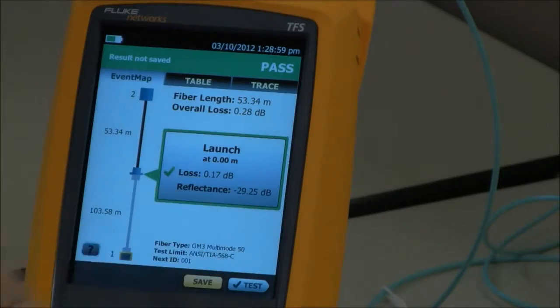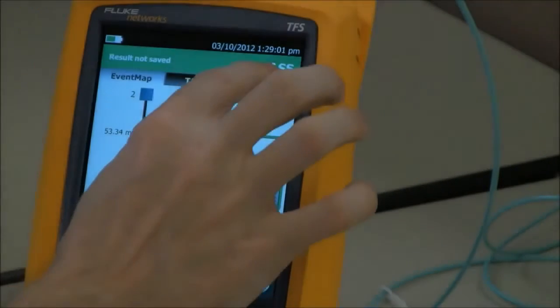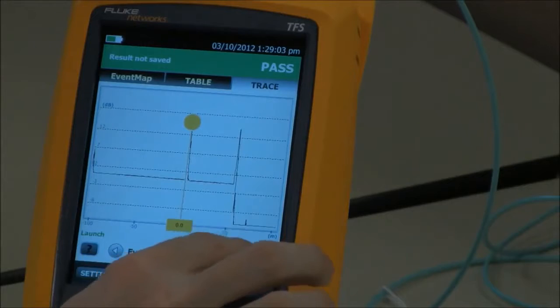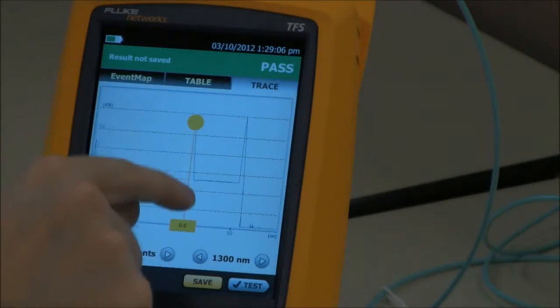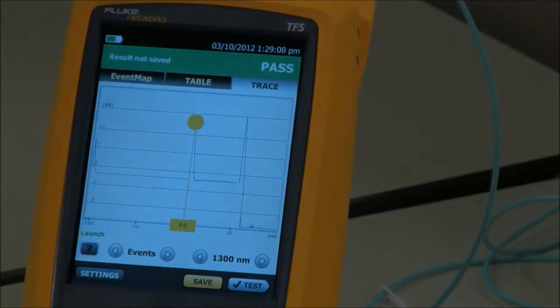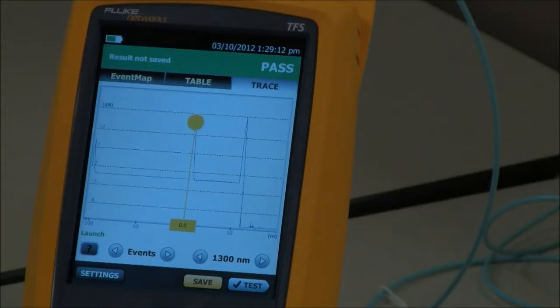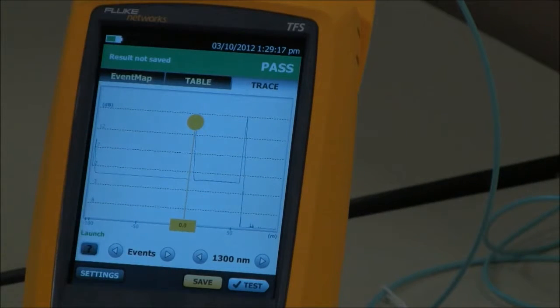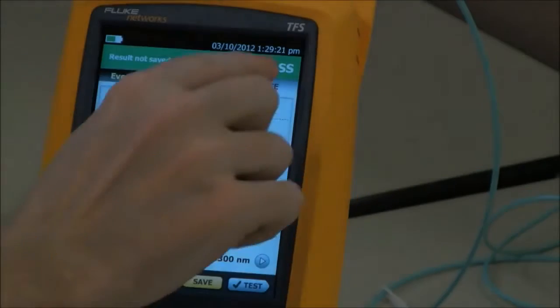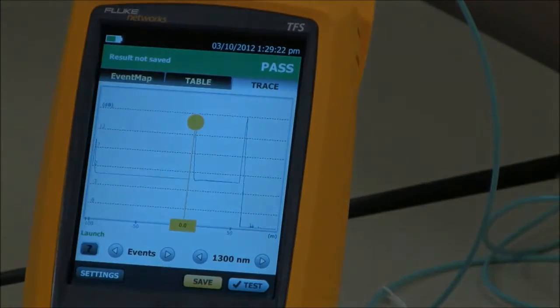This reflectance could be all the way down to minus 15 dB and it still would not fail. At minus 29.25, when we look at the trace, particularly at 1300, we see that we have a very large spike here, indicative of reflectance. There are many OTDR folks out there who would look at this and say, I'm not going to accept that — that's too much reflectance. Yet why did your tester come up with a pass?